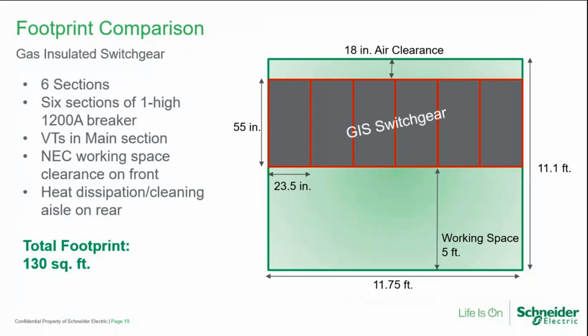If I do the same application with gas insulated switchgear, now I'm looking at a design that's front access only, 1 cubicle each for the circuit breakers, and then a VT section underneath the main breaker on the far left. NEC working clearance on the front, but just basically heat dissipation space on the back, looking at 130 square feet of space. So quite a bit of reduction versus that 211 square feet.